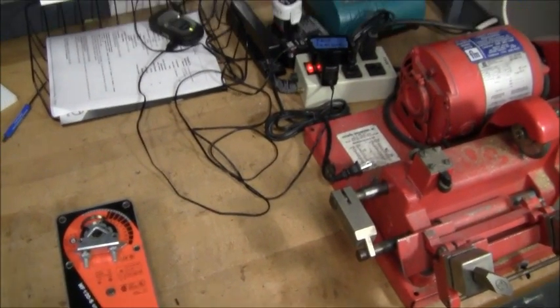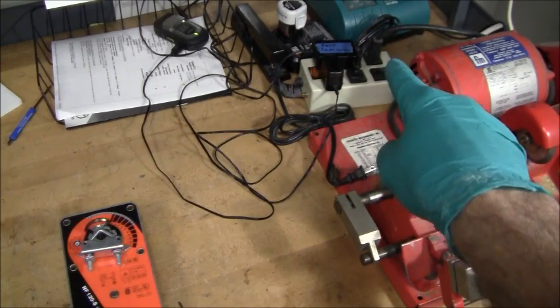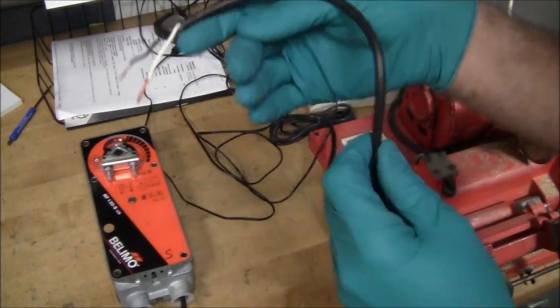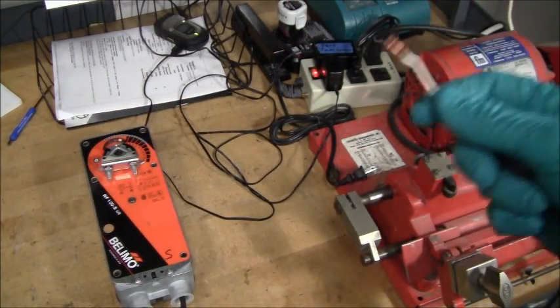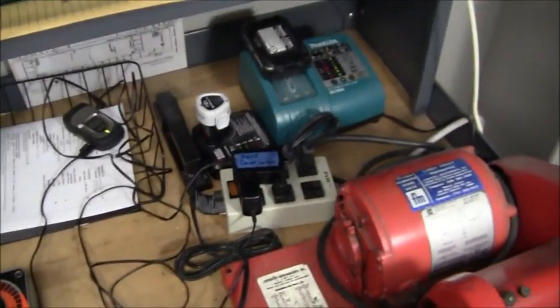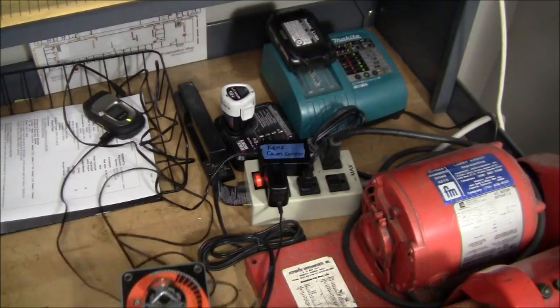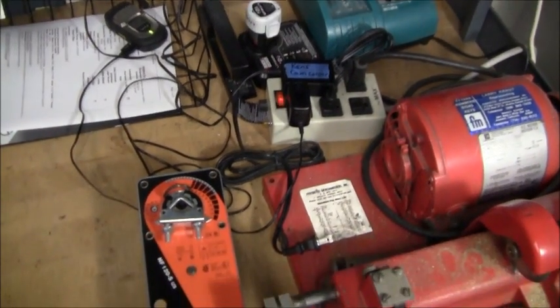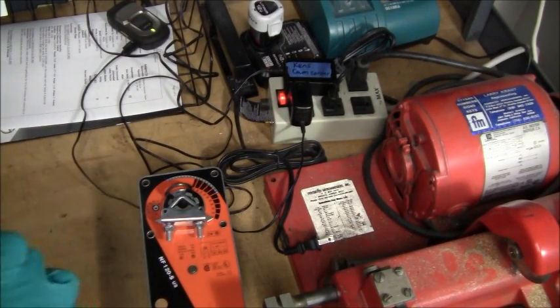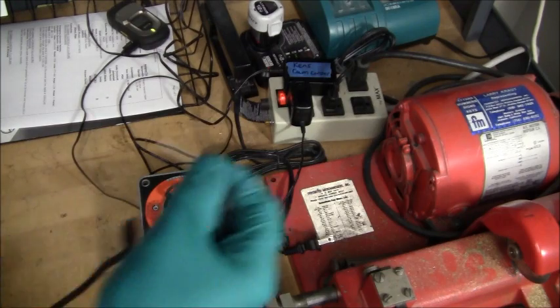Now that I've got this on the table, let me show you how to do a tabletop test of this motor. You can see I've got 110 volts. I'm going to take the motor leads, hot and neutral, and put them directly into the power source and this should operate. I need to verify that I have 110 volts coming out. I'm wearing gloves for additional protection.